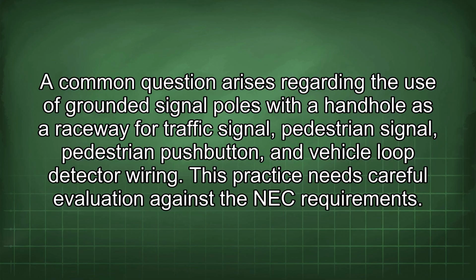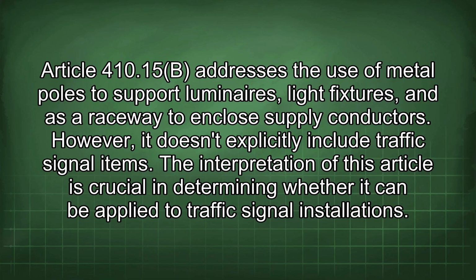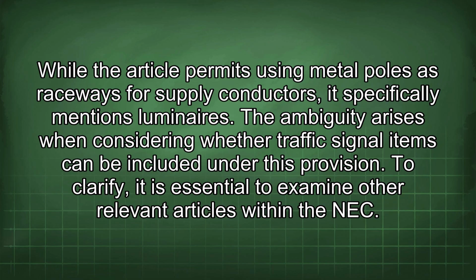This practice needs careful evaluation against the NEC requirements. Article 410.15b addresses the use of metal poles to support luminaires, light fixtures, and as a raceway to enclose supply conductors. However, it doesn't explicitly include traffic signal items. The interpretation of this article is crucial in determining whether it can be applied to traffic signal installations. While the article permits using metal poles as raceways for supply conductors, it specifically mentions luminaires. The ambiguity arises when considering whether traffic signal items can be included under this provision.